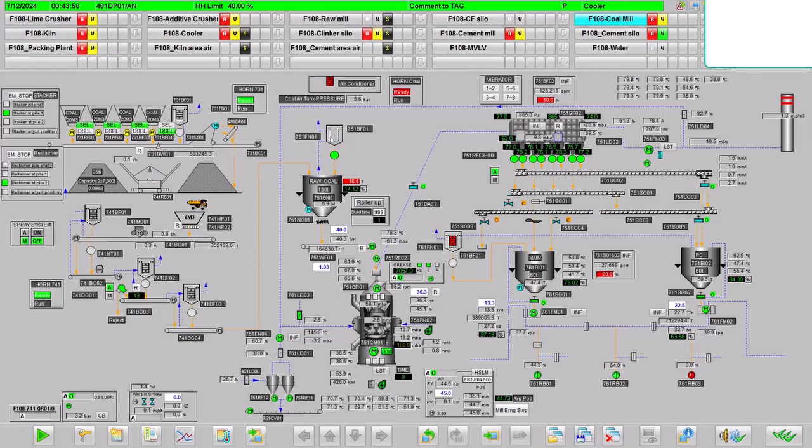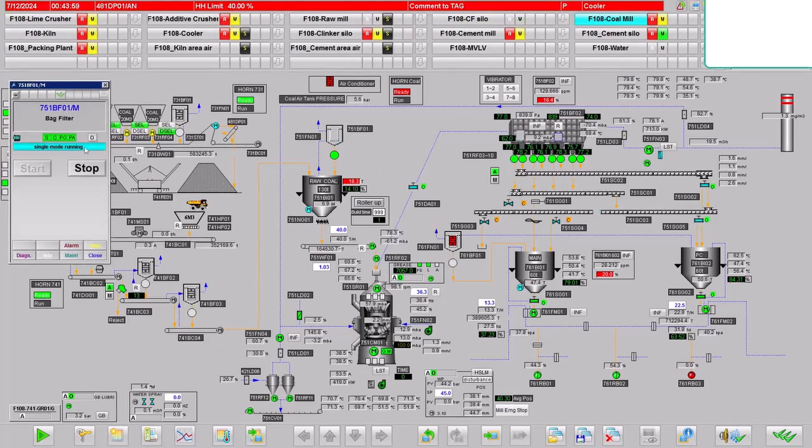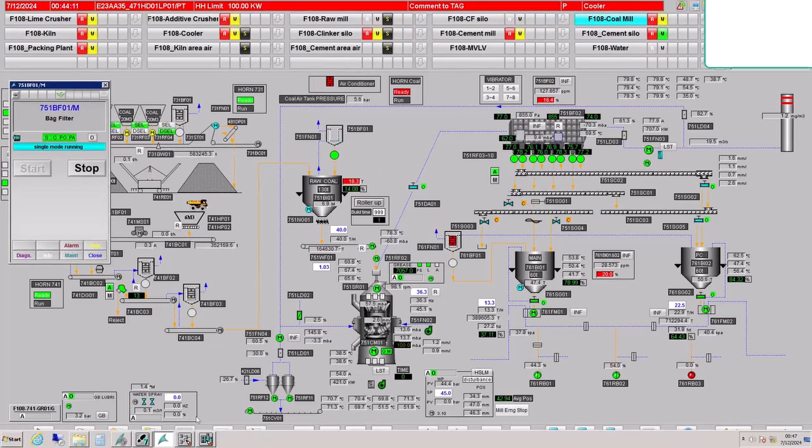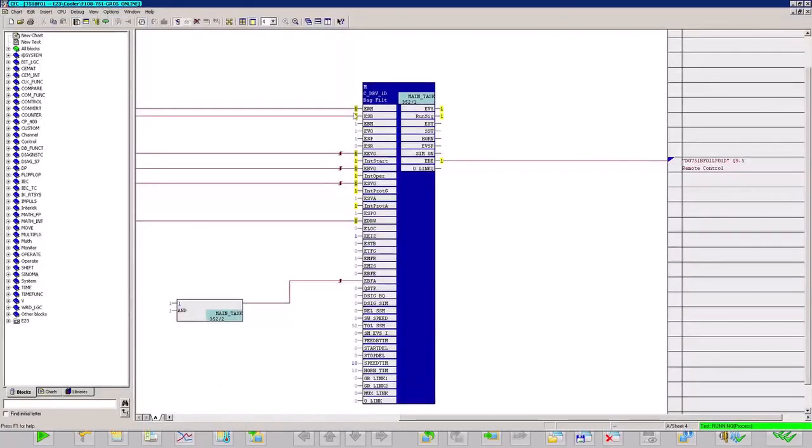This is how I can observe the online status of any equipment on my PLC HMI or SCADA HMI. This is necessary because at times operators may ask you to observe the status or diagnose a fault. As a PLC engineer or PLC technician, you will have to trace the equipment from HMI to the CFC logic, and this is how you do it.